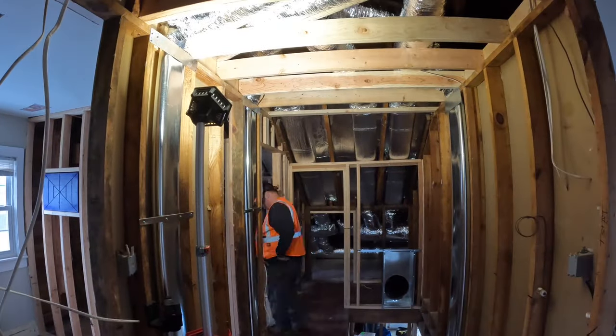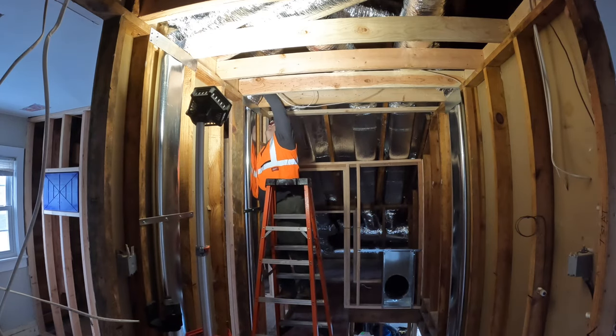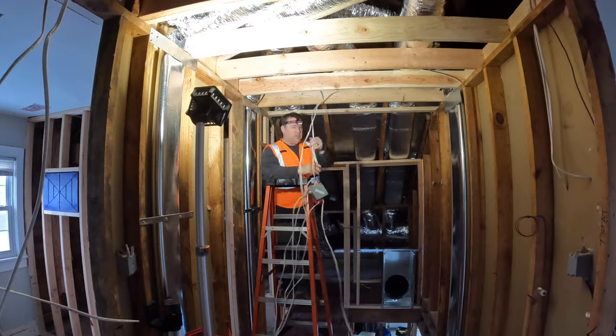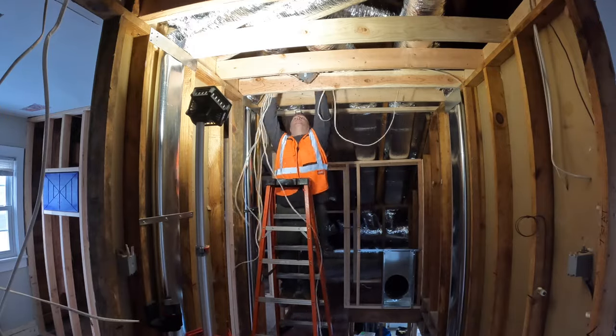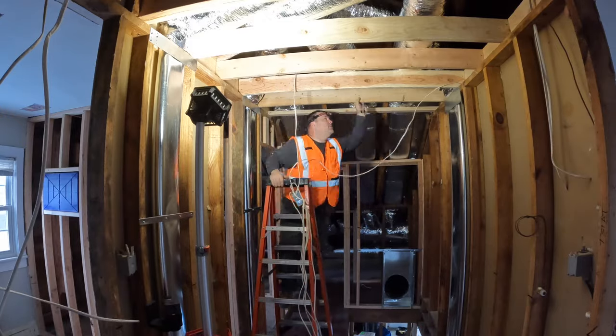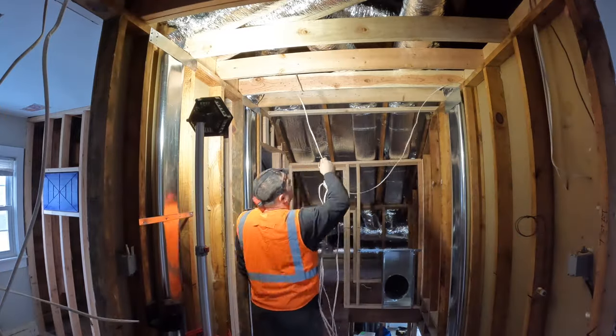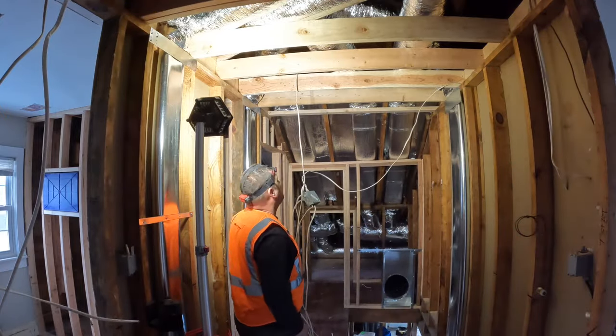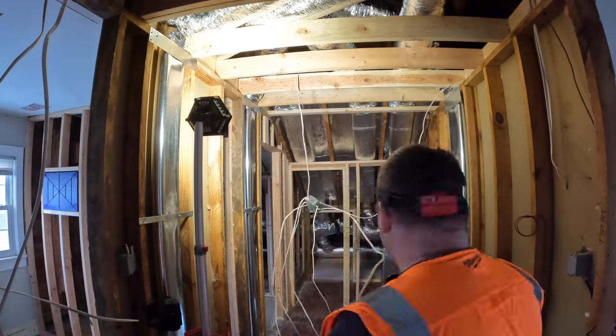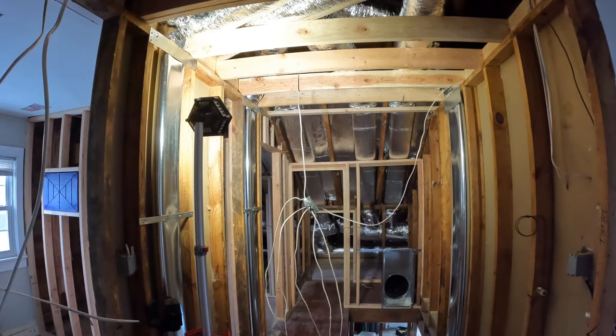It was very common in older houses like this that didn't have forced air heating and cooling. You didn't have cooling in the 1920s - that's the first thing. But you had heat - most of that heat was from a boiler, which is what they had here, and that's all coming out. So when you don't have a forced air system, what you need to do is put in window air conditioning units and you're going to need dedicated circuits for that. What we would do is run conduit up to a receptacle on the outside of the house so you can have that dedicated circuit for the air conditioner.